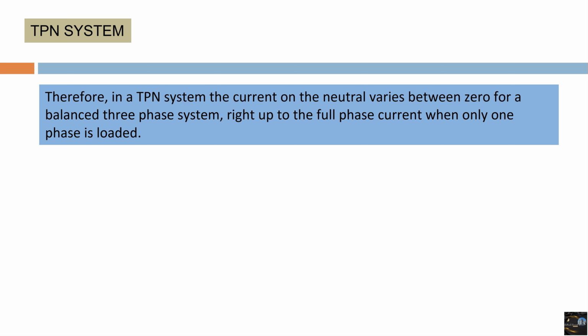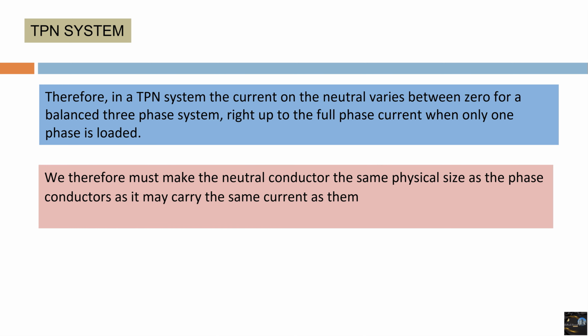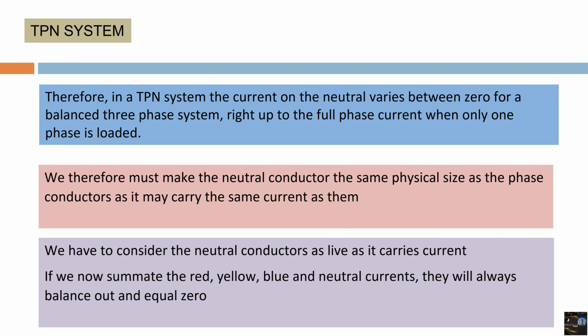Thus, in short, in a TPN system, the current on the neutral varies between 0 for a balanced three-phase system right up to the full phase current when only one phase is loaded. We therefore must make the neutral conductor the same physical size as the phase conductors, as it may carry the same current as them. Therefore, we have to consider the neutral conductors as live as they carry currents. If we now summate the red, yellow, blue and neutral currents, they will always balance out and equal zero.